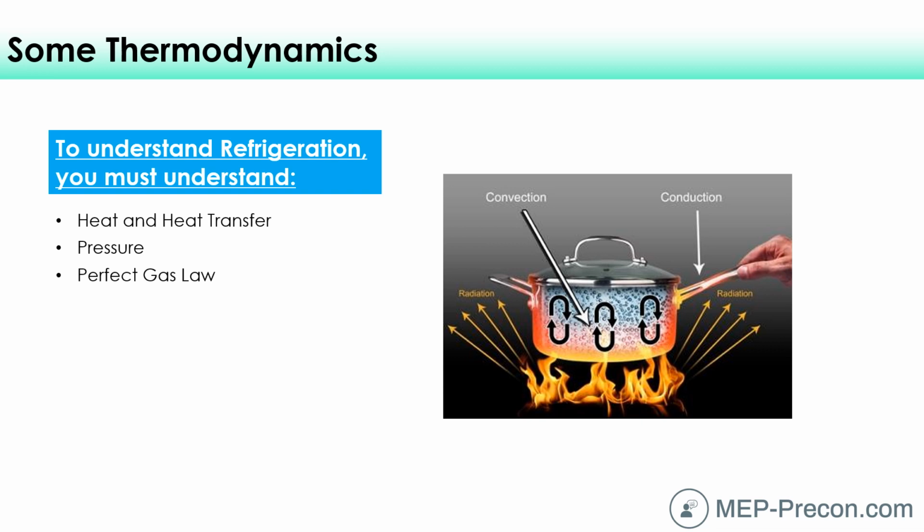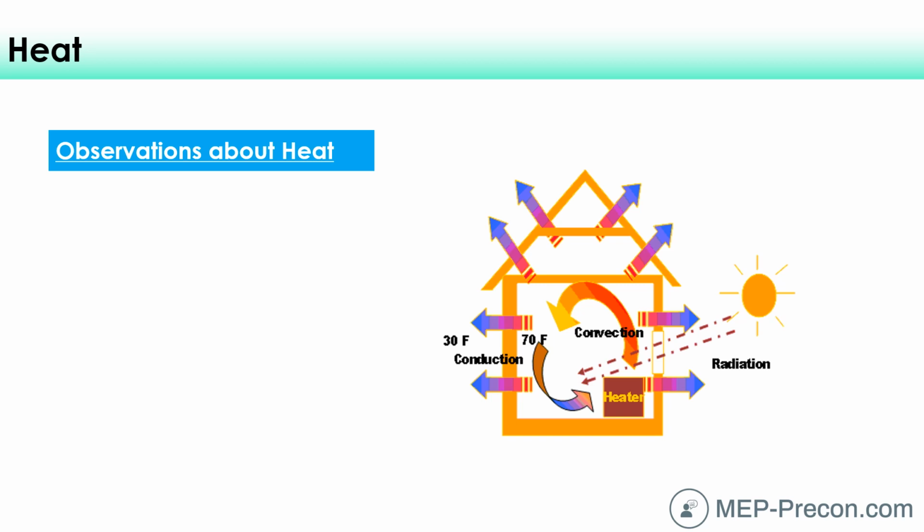And let's talk about heat first of all. If you're not familiar with the concept of a BTU, a British thermal unit, let's talk about that first, because you'll hear about that a lot in our industry, as well as these videos here. So a British thermal unit is the amount of heat that it takes to raise 1 pound of water, what do you think, 1 degree Fahrenheit or Celsius? 1 pound of water, 1 degree.